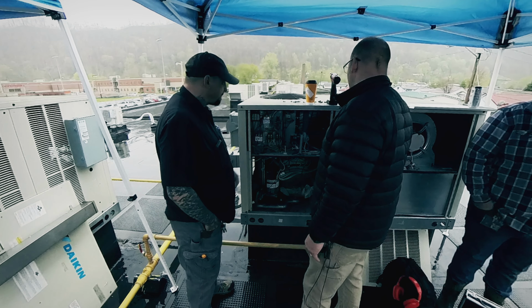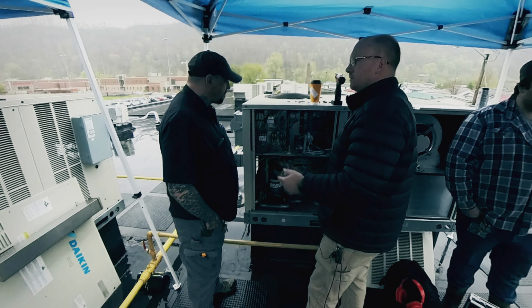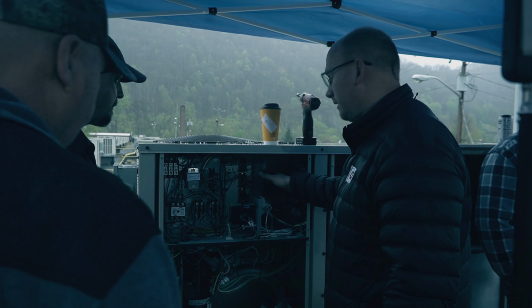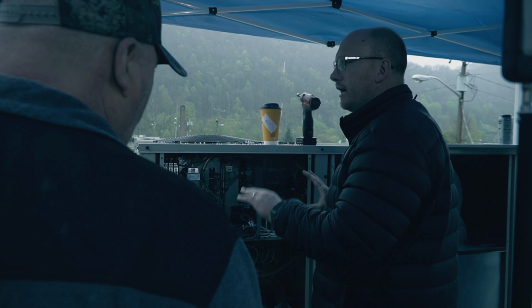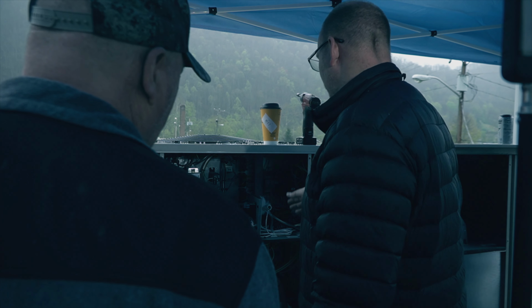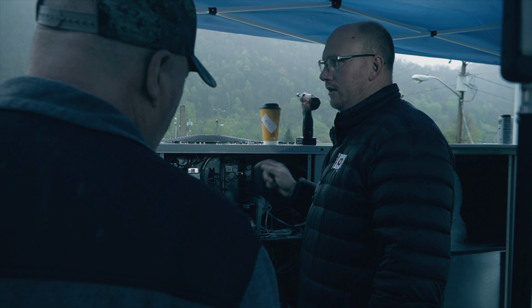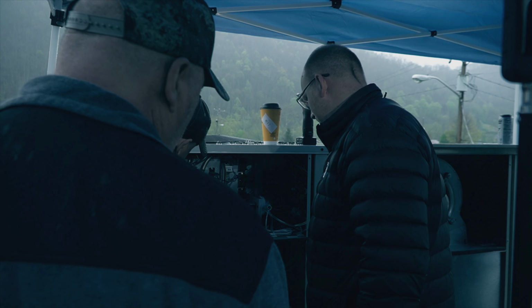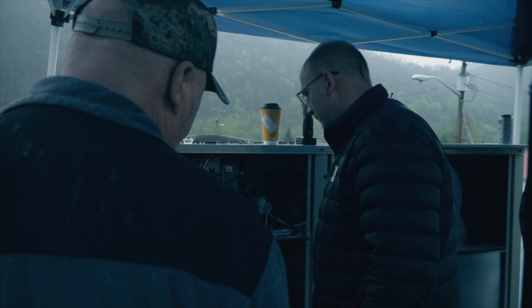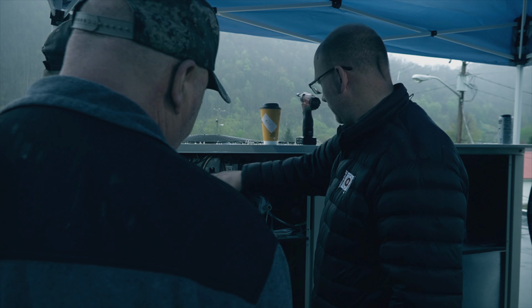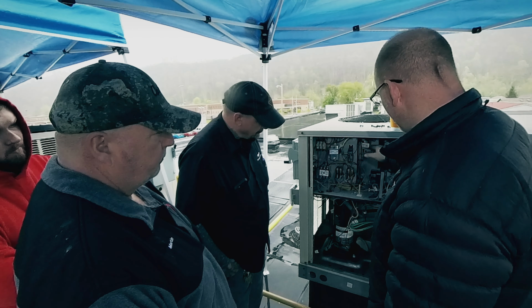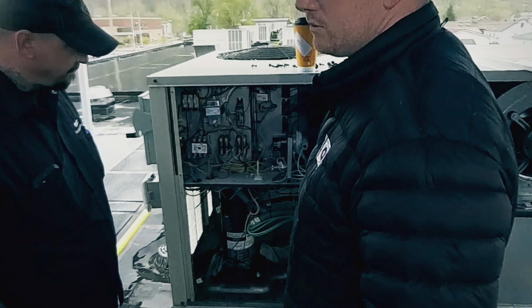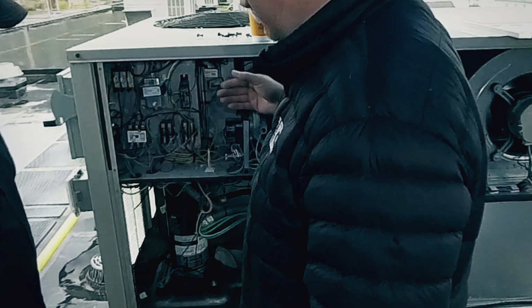These style units are here at the middle school. Over at Logan Middle, instead of this, it's going to have a Microtech, and that's a whole different ball game. You can manually go into your Microtech and turn on your fan, ramp your fan up, turn on your cooling, and ramp your cooling up and down. There are your two transformers: one is for our controller, one is for the unit. These new controls pull a lot more VA than the old stuff, so you can't really tie onto an existing transformer anymore.